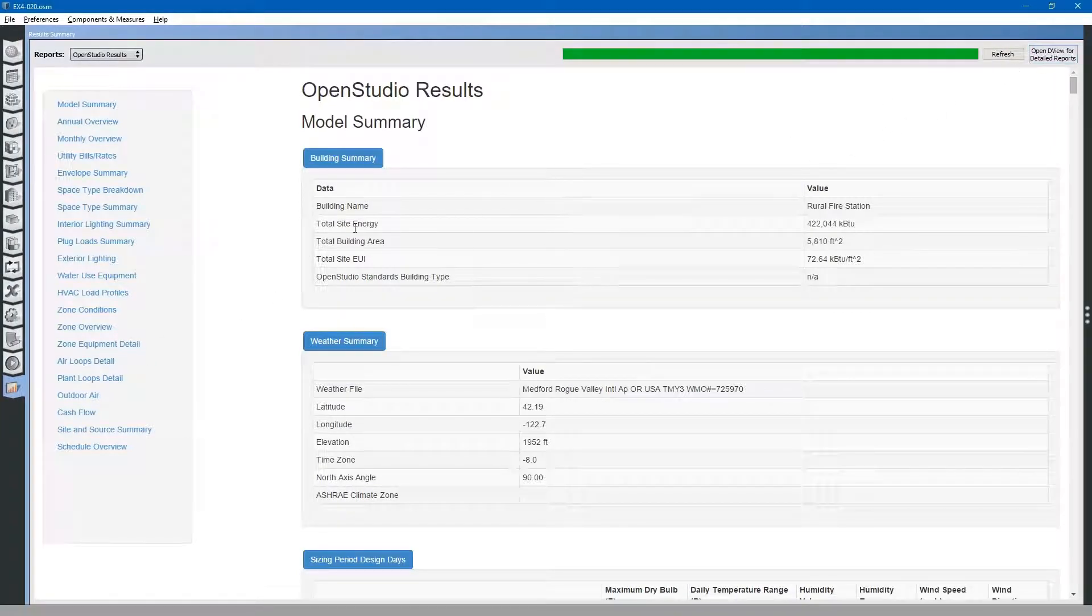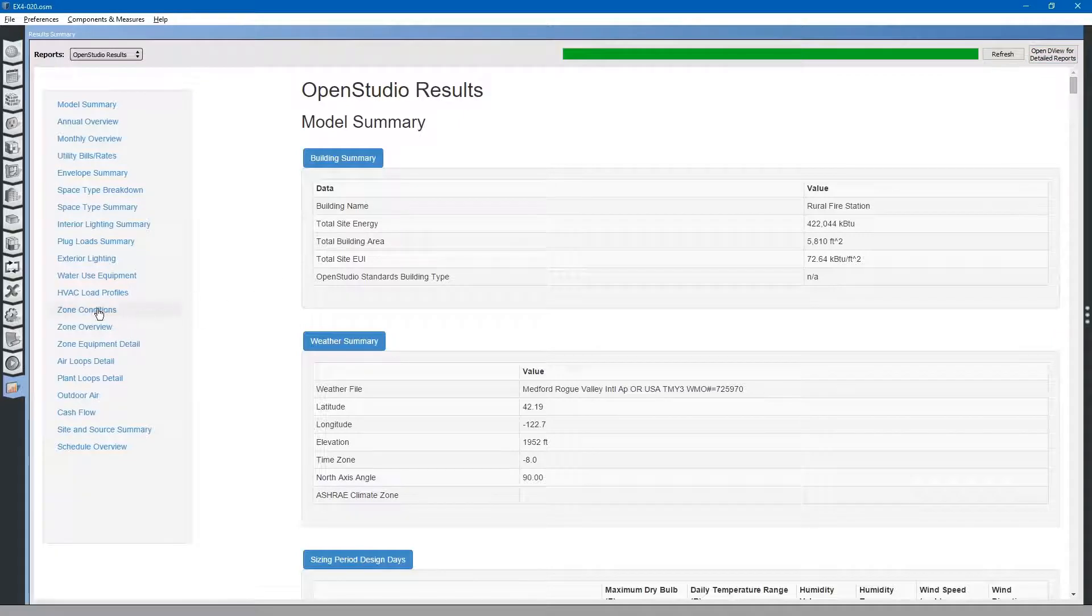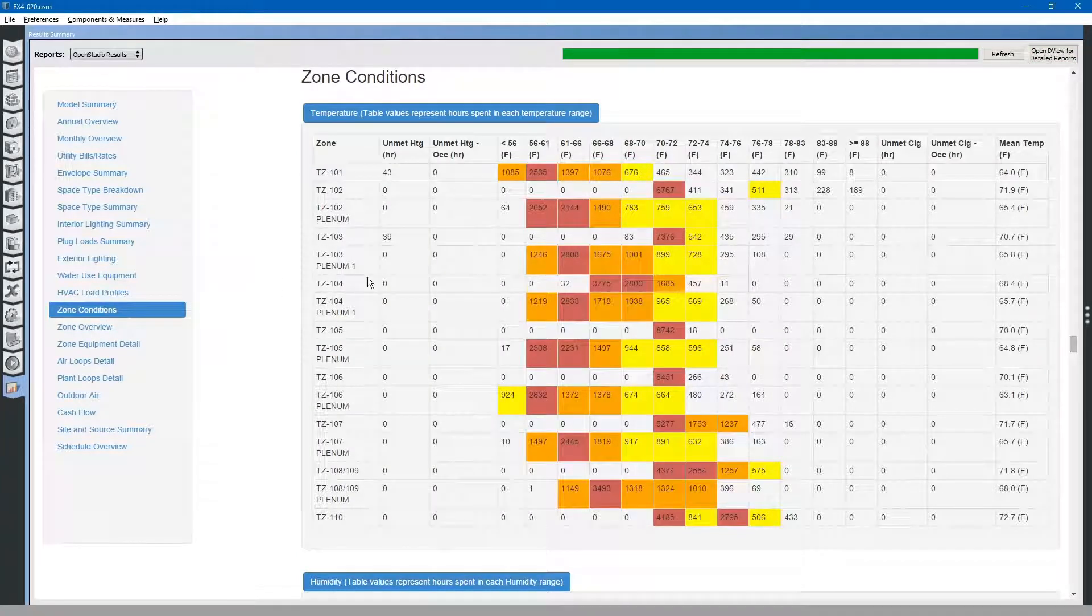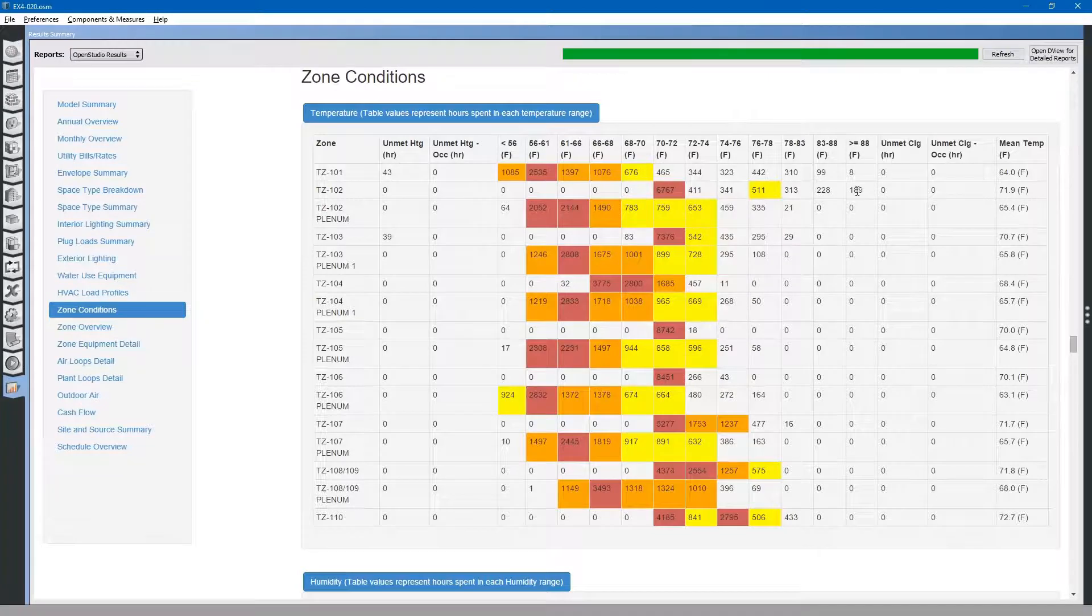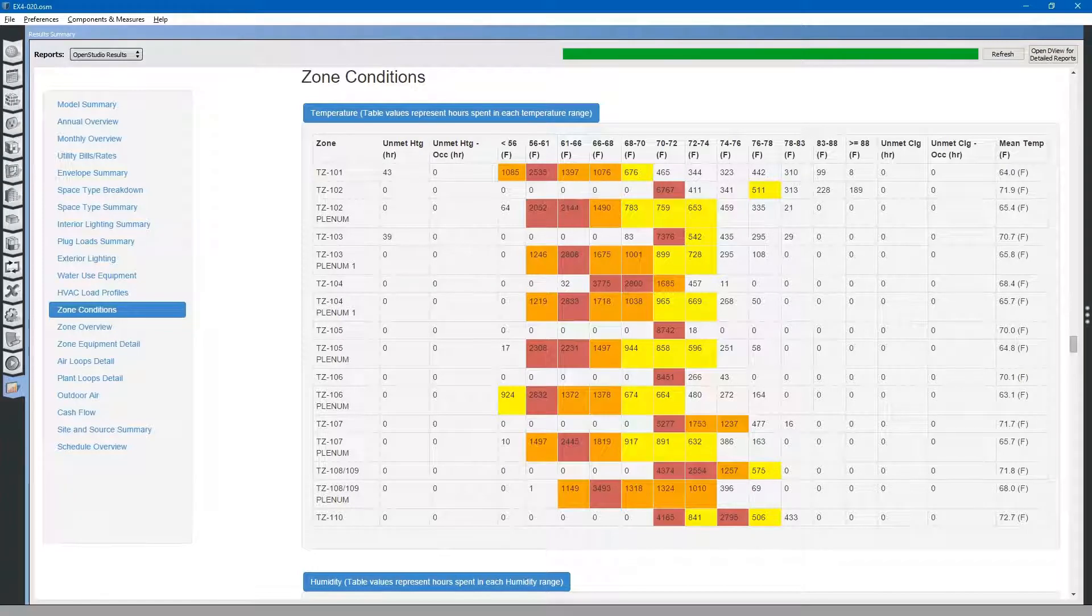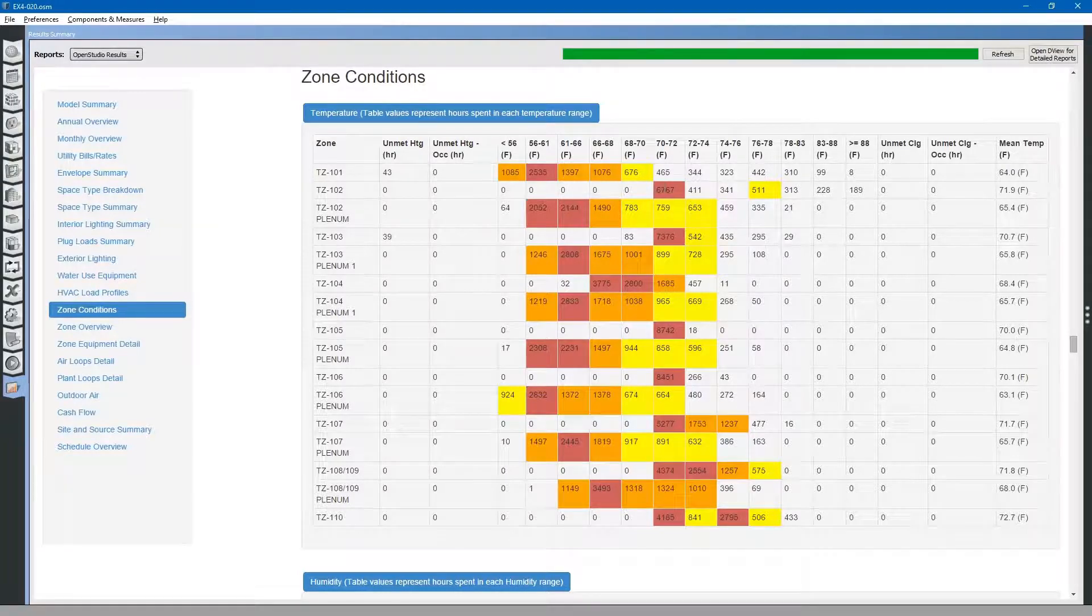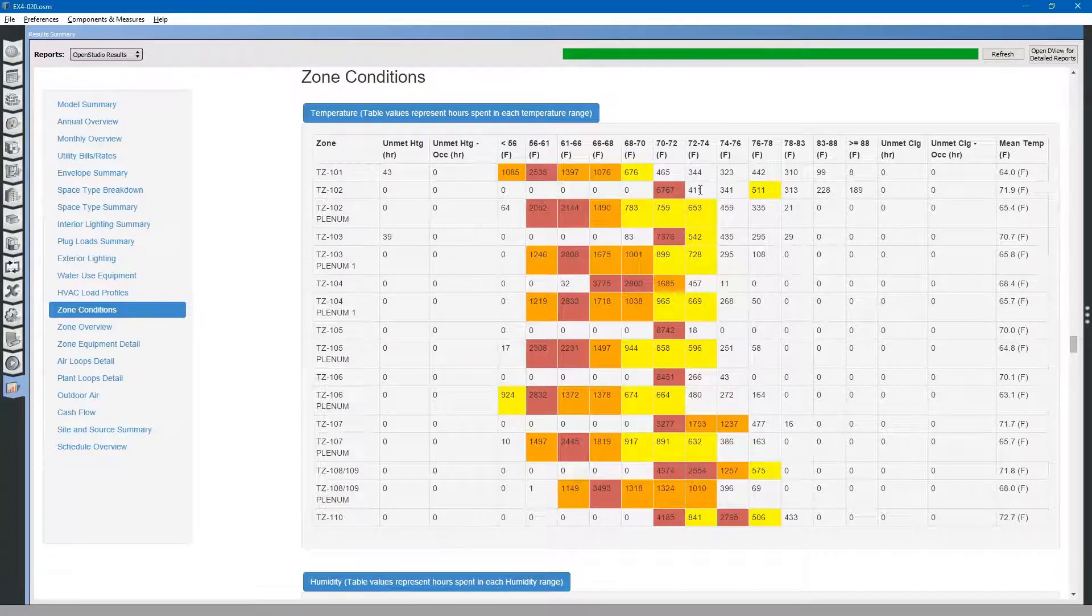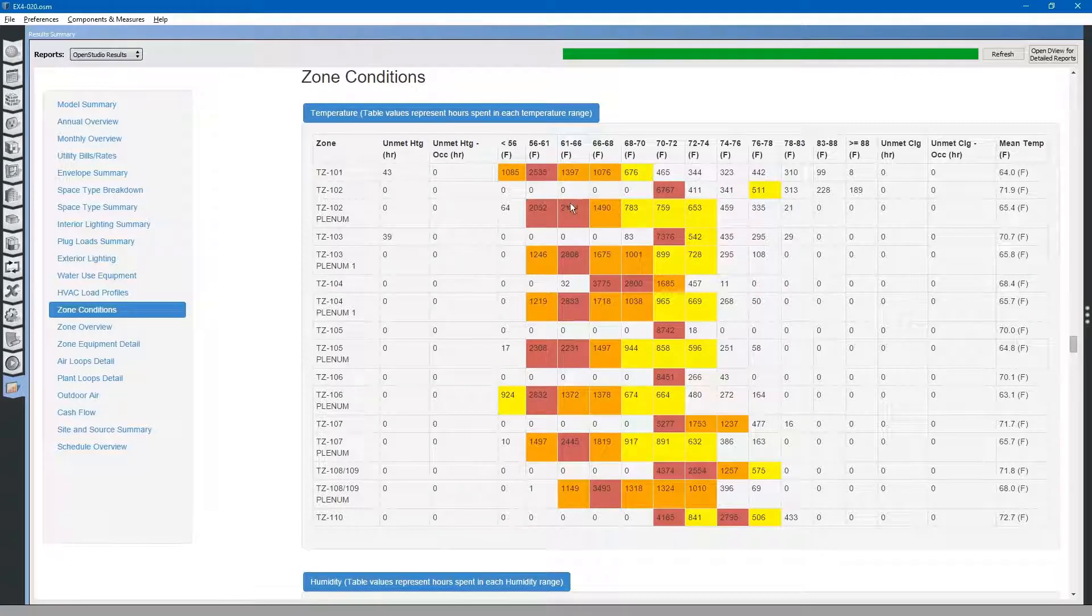Actually, let's take a look at zone conditions. You can see that our unmet hours during the high temperatures have dropped significantly. The zone temperatures have coalesced into the low 70s. Let's go to DView.